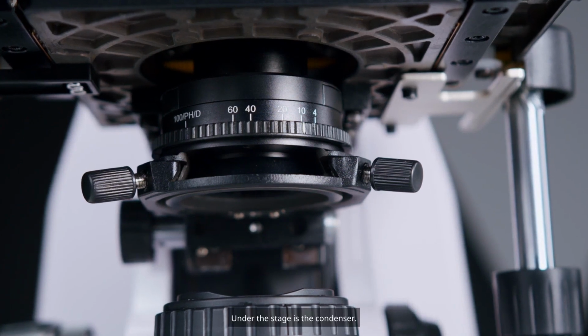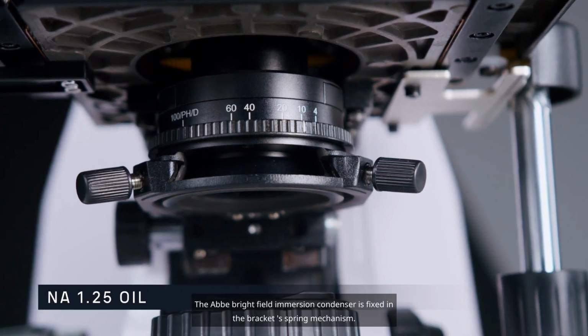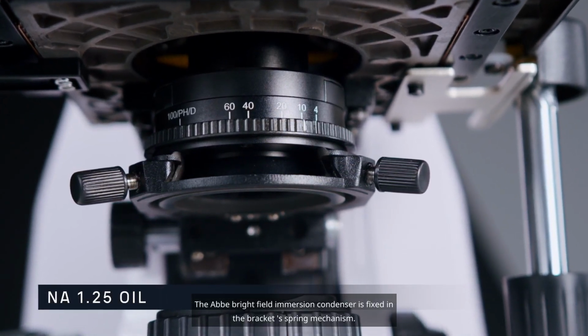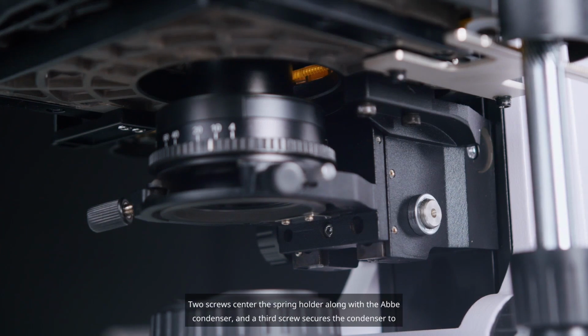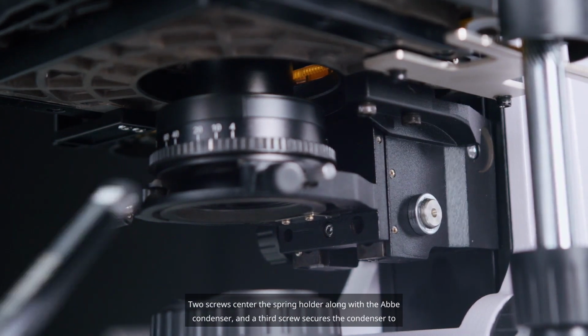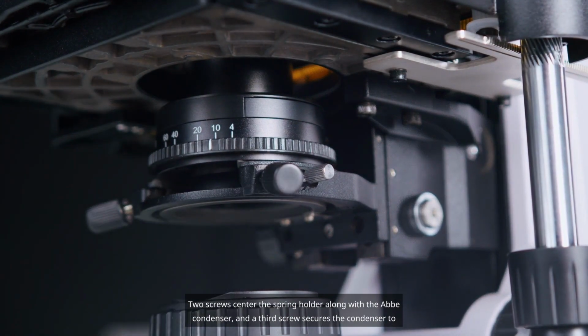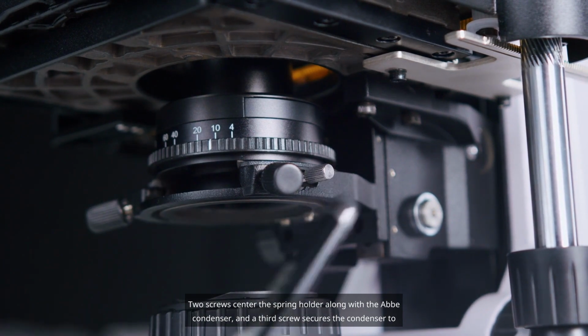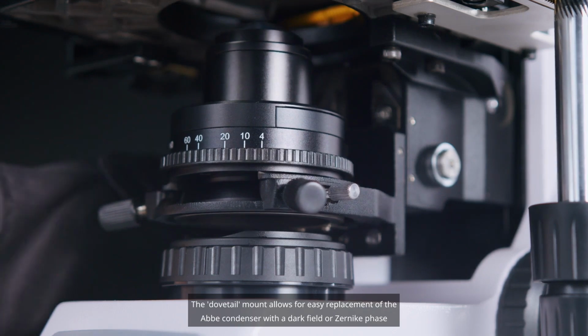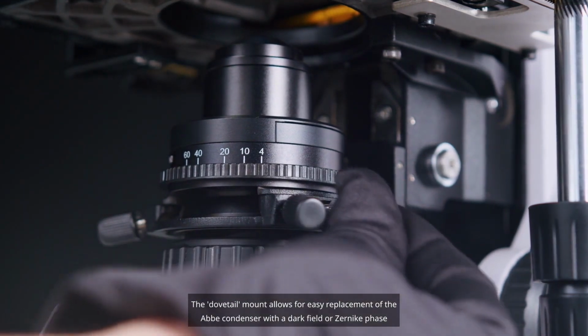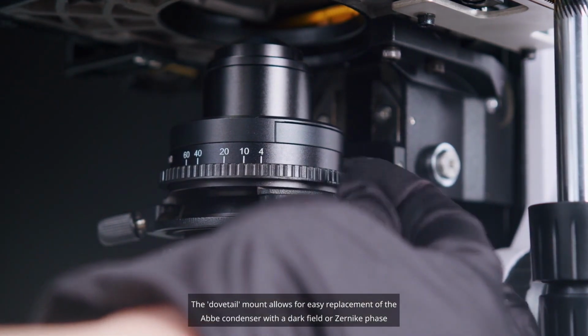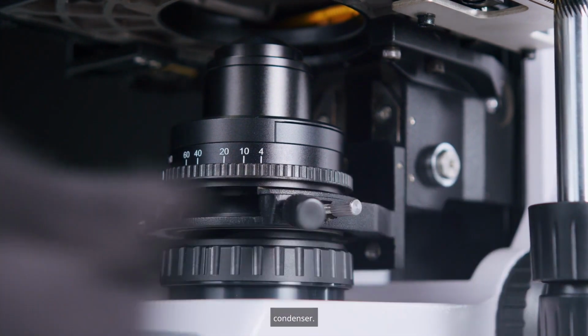Under the stage is the condenser. The Abbe Bright Field Immersion Condenser is fixed in the bracket's spring mechanism. 2 screws center the spring holder along with the Abbe condenser, and a 3rd screw secures the condenser to the holder. The dovetail mount allows for easy replacement of the Abbe condenser with a dark field or Zernike phase condenser.